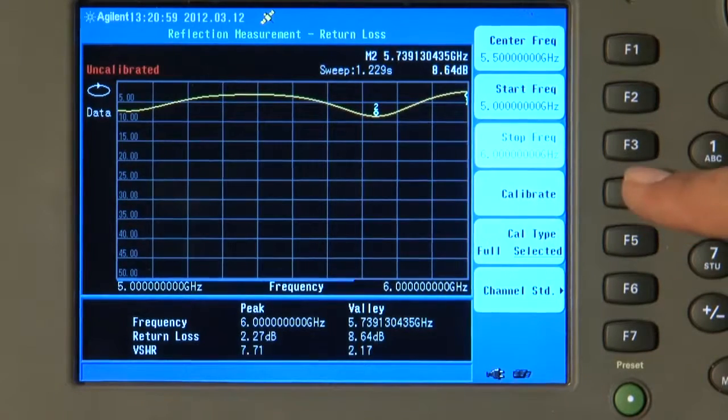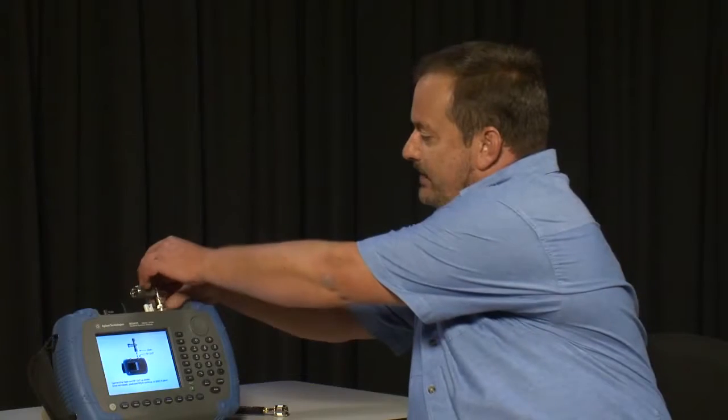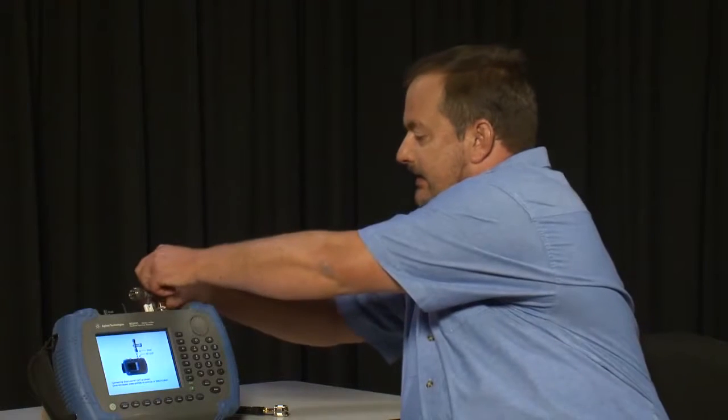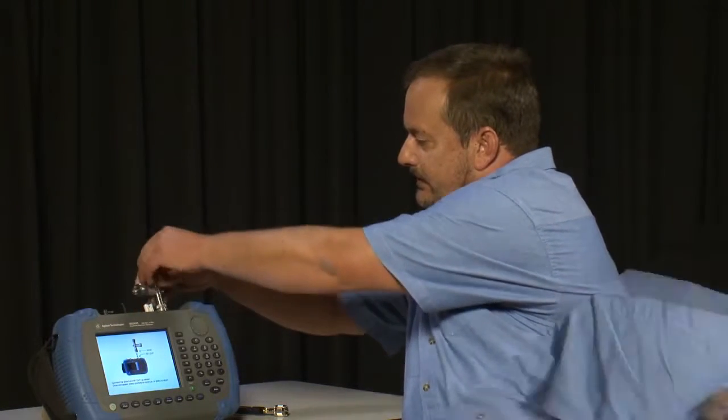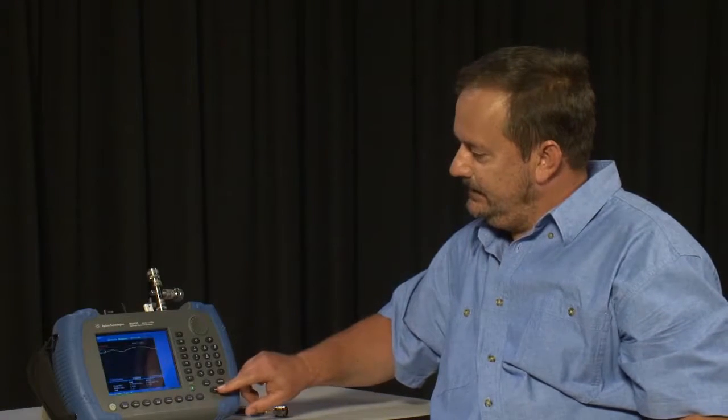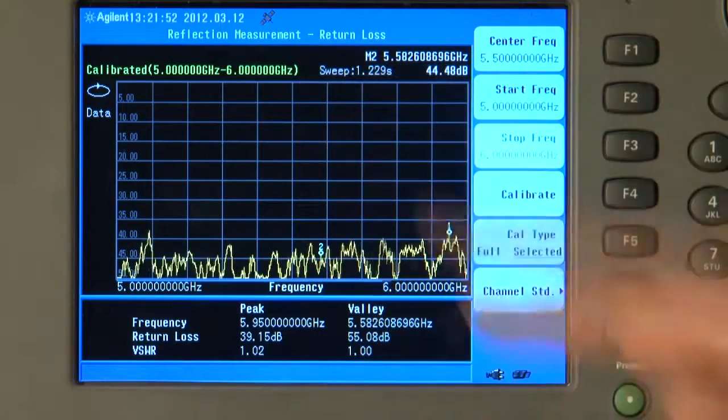So we press Calibrate and follow the on-screen instructions. We connect an Open and press Enter, and we connect a Short and press Enter, and we connect a Load. And now the instrument is calibrated between 5 and 6 GHz.